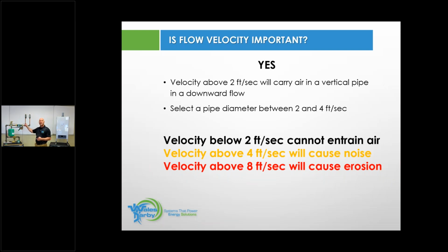It's not going to marry up perfectly to the pipe like our VT temperature sensitive circulator will, but it will reduce the flow a little bit. So that will throw even another wrench into this. But if we stick to that piping diagram with the 2 to 4 feet per second, that's really important, and it will definitely give you a great designed and operating system.